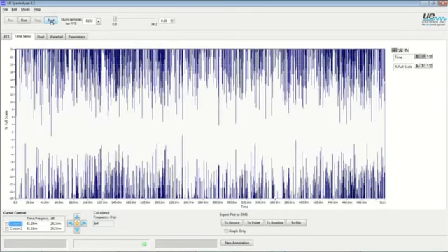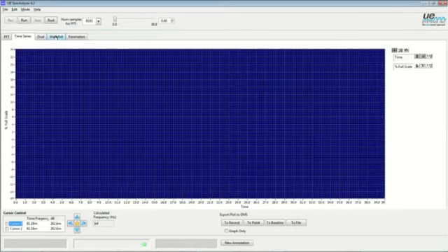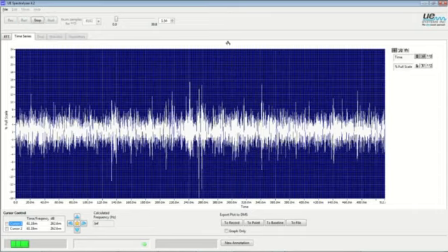And as we see on this one, the signal on the second recording was overloaded. And that creates some problems as well, which I will caution everybody on. When you make these electrical recordings, it is critical not to overload the signal in the spectralizer. What happens is you get chopping on the top and bottom of the analyzer, what's commonly known as square waving. And when you chop that data off, you cannot determine fluctuations or variations in the amplitude that I'm about to talk about. So I will play the first recording in the time analyzer.